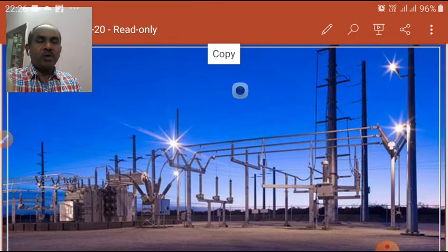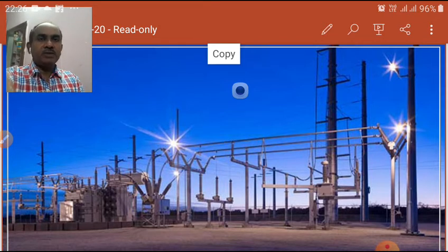Last class we saw one problem, a 500 meters, half kilometer line, in a vertical manner with one cut point and one extra straight line. We calculated the number of poles, number of insulators, length of ACSR conductors, and number of stays. We calculated and tabulated all things. That means we made one schedule also.